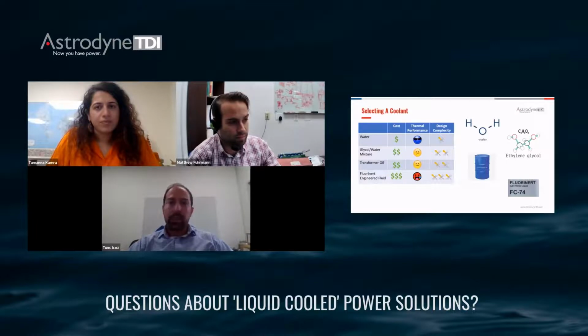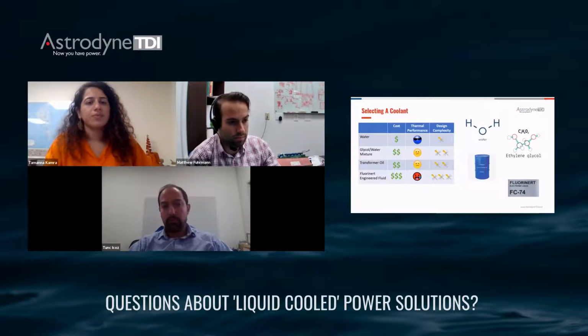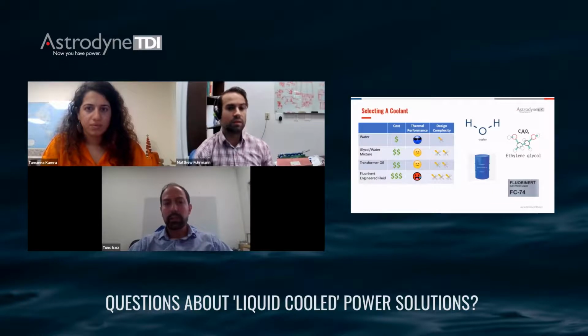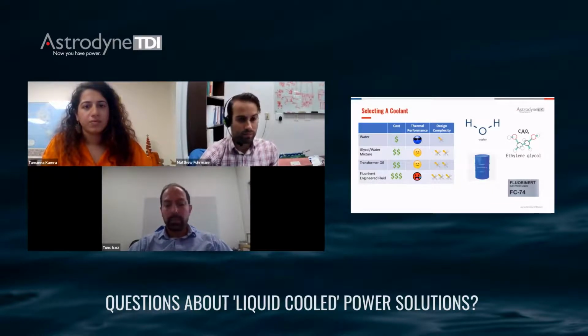The answer is they have special applications where, because of the insulating properties, you can submerge the components directly in these fluids. The benefit is that when you bring the coolant into direct contact with the component, your thermal and cooling performance gets enhanced significantly. So there's a trade-off: the liquids themselves aren't that great thermally, but the fact that you can bring them into direct contact with the components offsets that deficiency. So those are used in certain niche applications. Transformer oil is widely used in big transformers, obviously, but also in power supplies, especially for outdoor applications.